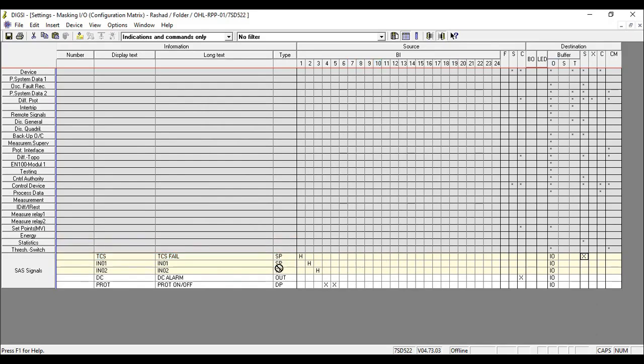So this is the first signal. The second ones, the source was a binary input, but the destination is CFC. I will clarify these two for CFC in this way. After that, for the alert, the source will come from CFC, but the destination in SAS, you will tell it X. This is right, this is for CFC, so I will send both of them to CFC in this way.